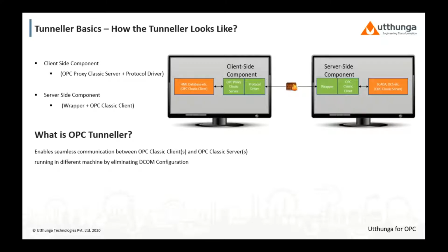So we will be deploying a server-side component which will be communicating locally with the OPC classic server, having an OPC client as a driver, and there will be one wrapper. The other end will have a client-side component with an OPC proxy classic server which connects to an HMI application locally, and it will have a protocol driver which can communicate to a wrapper through the firewall.